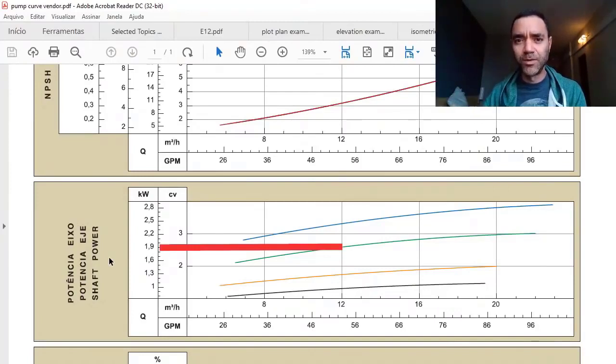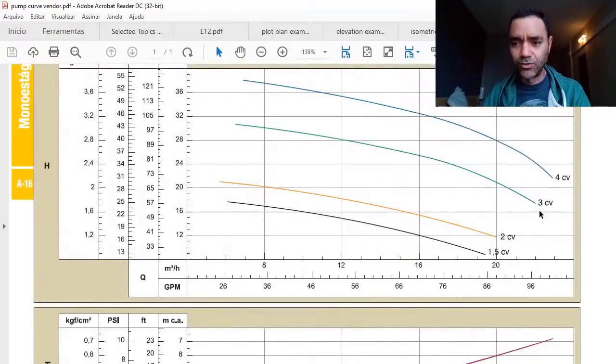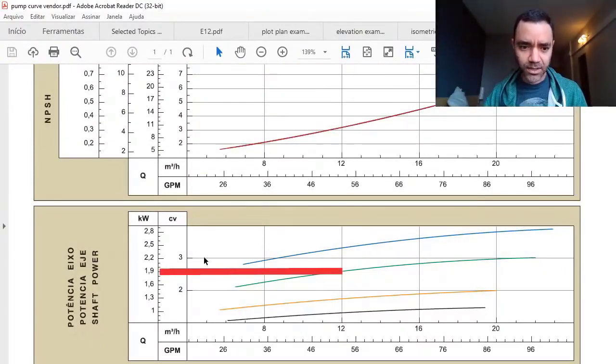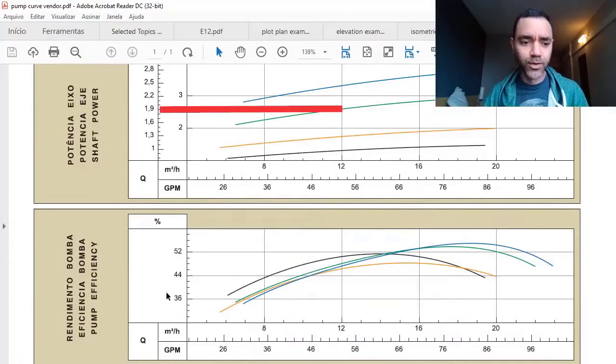Here, the vendor considered the motor size—the green line is the motor size—is 3 CV as the maximum shaft power. You can see the motor size is 3, but for this point of the curve I will not consume 3 CV, I will consume around 2.5 CV. Finally, we have the pump efficiency. At this point, we have around 45 to 48 percent of pump efficiency.